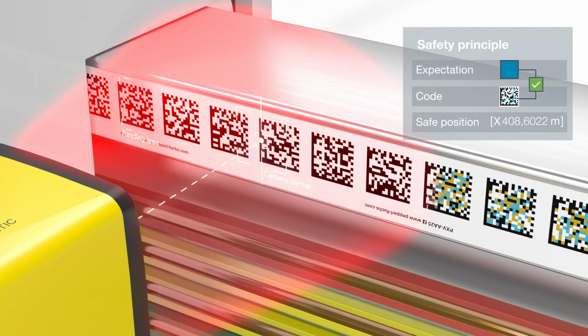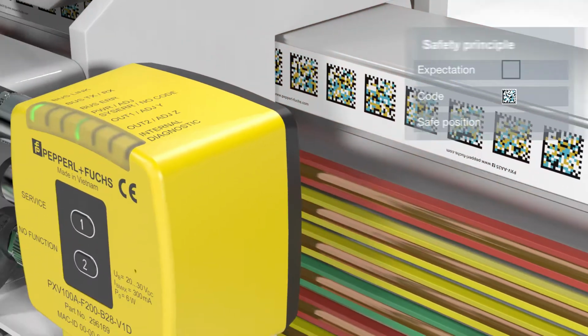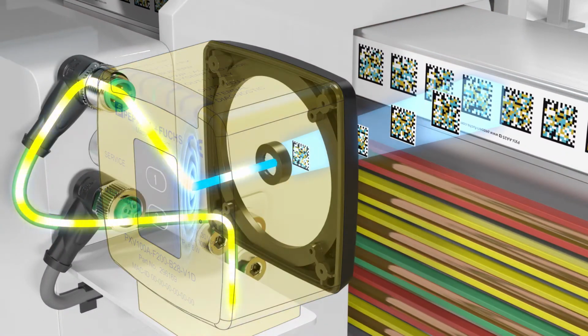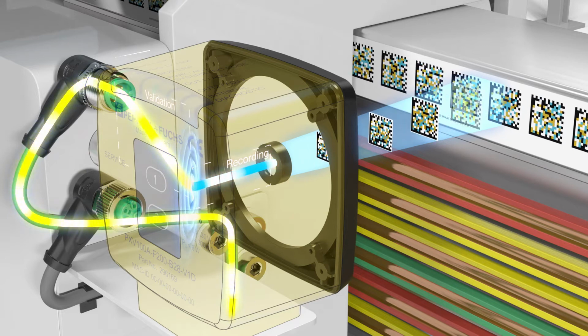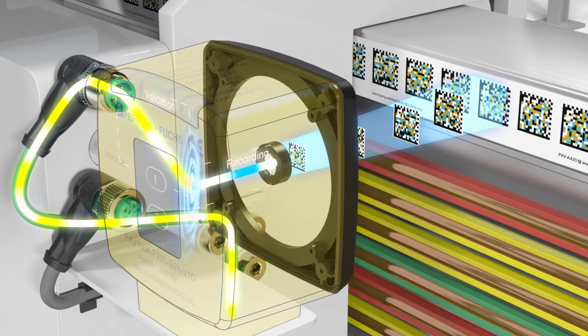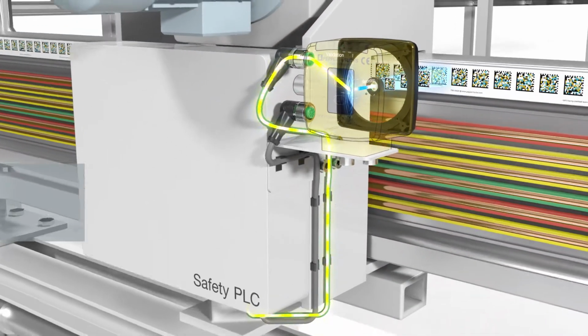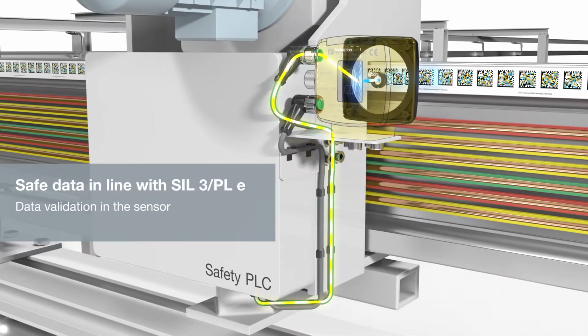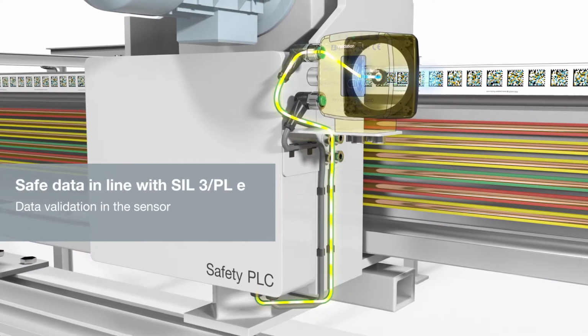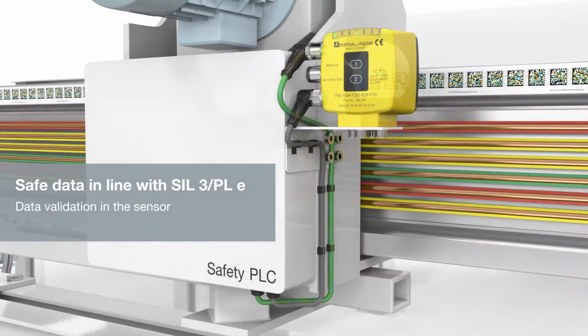Plausibility tested directly in the sensor, the safePX position is transferred to the safety PLC. The data can then be processed in the PLC without additional plausibility checks. This allows the system to achieve SIL 3 PLe rating with just one sensor.